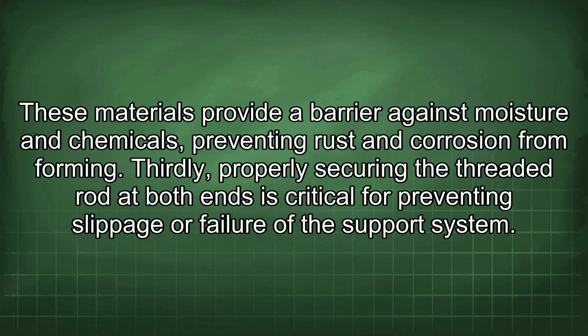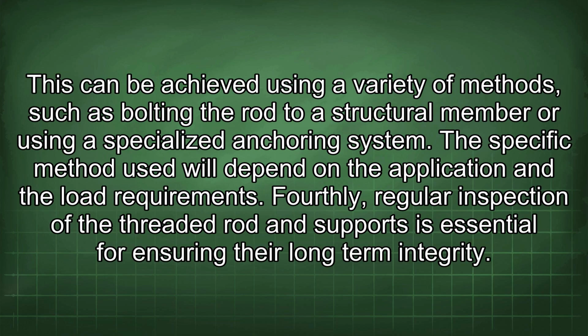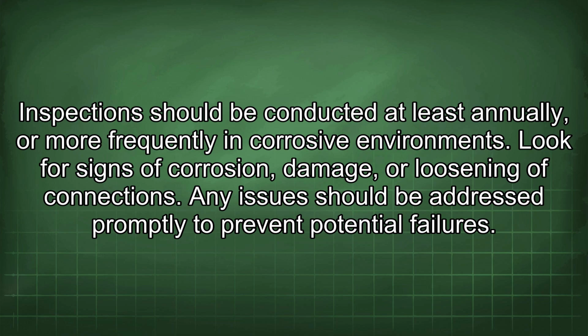Thirdly, properly securing the threaded rod at both ends is critical for preventing slippage or failure of the support system. This can be achieved using a variety of methods, such as bolting the rod to a structural member or using a specialized anchoring system. The specific method used will depend on the application and the load requirements. Fourthly, regular inspection of the threaded rod and supports is essential for ensuring their long-term integrity. Inspection should be conducted at least annually or more frequently in corrosive environments. Look for signs of corrosion, damage, or loosening of connections. Any issue should be addressed promptly to prevent potential failures.